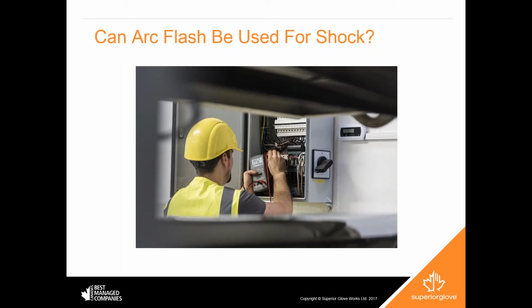The evaluation and the actual boundaries that your employee might be performing will obviously dictate the level of glove and protection that you might want to look at, because there are arc flash gloves, probably level 2s all the way up to the level 4s, gloves now that are up in the 40 plus cal rating range. Matt?